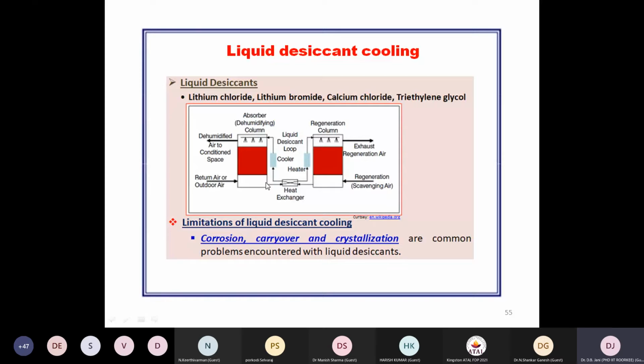The same weak desiccant solution is provided to the regeneration column for removing the water vapor by the flow of regeneration air from the bottom. So as exhaust air, moisture is removed from the liquid desiccant, and the strong liquid desiccant is collected at the bottom of the regeneration column and supplied back to the absorber column. Similarly, there is an alternate flow of strong and weak solution between the absorber column and the regeneration column, and the dehumidified air itself passes through the absorber column only, while the regeneration air is limited to flow through the regeneration column.